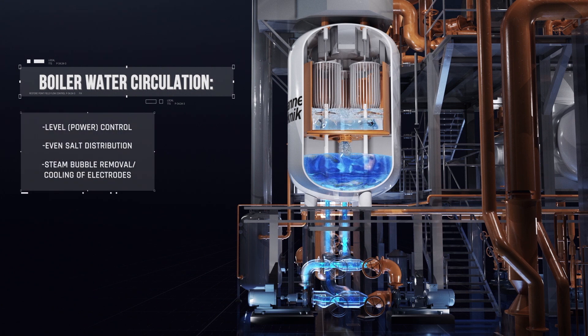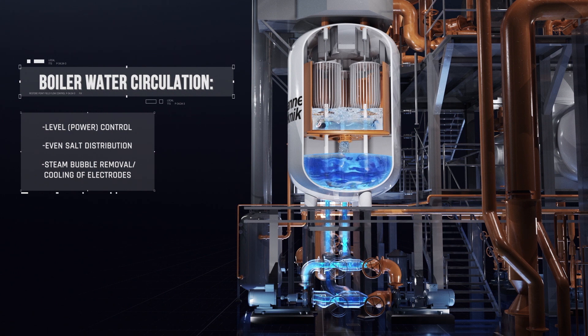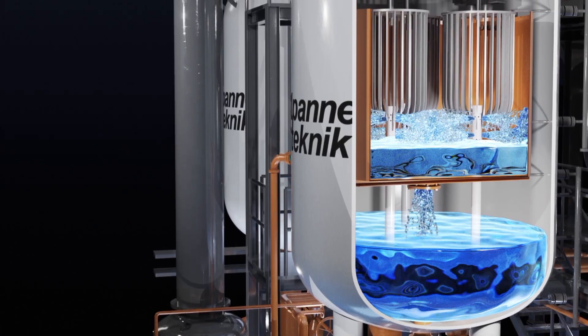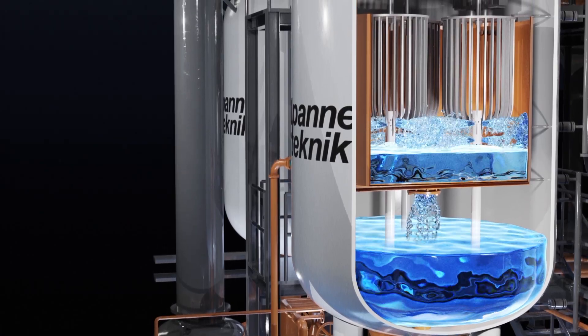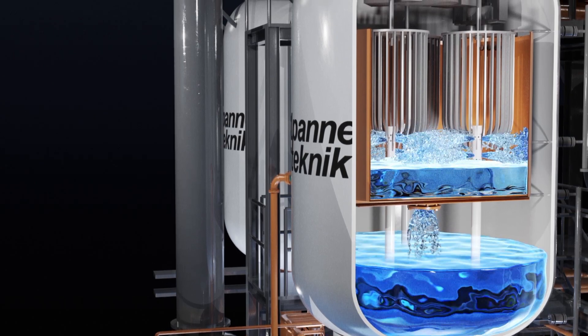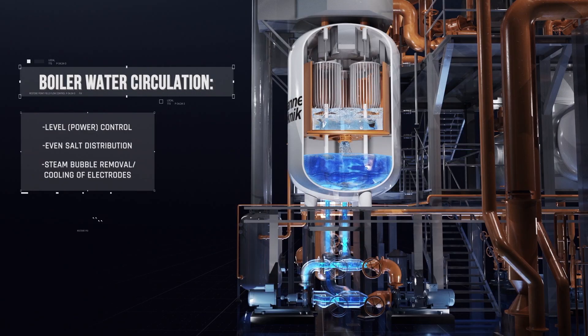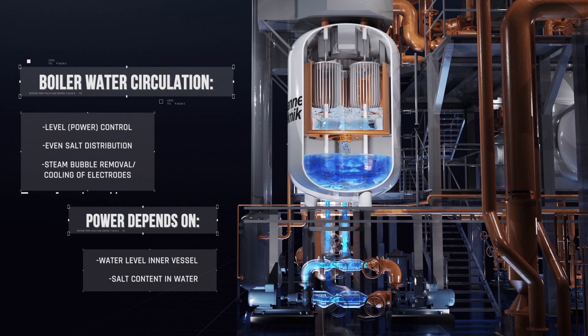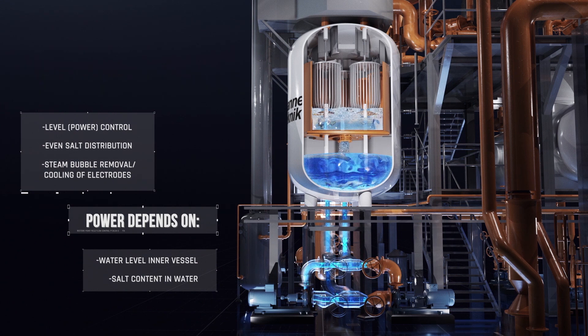The purpose of the circulation is to achieve an even distribution of salts in the water, needed to make the water conductive for steam production. The circulation also removes steam bubbles from the electrodes to improve operating conditions. The power of the boiler depends on the water level in the inner vessel and the conductivity of the water.